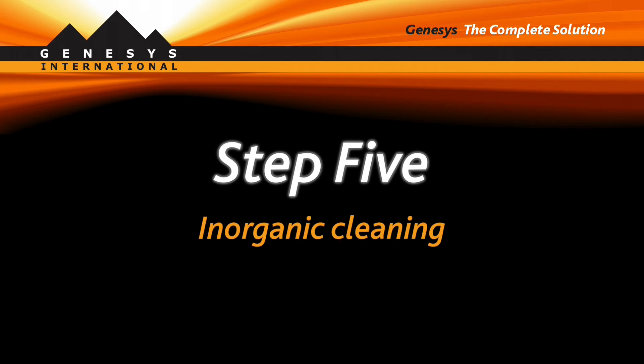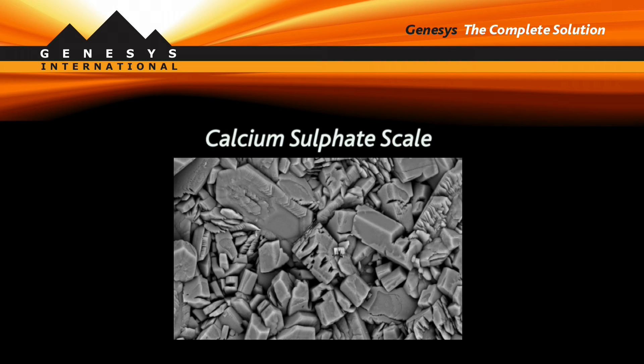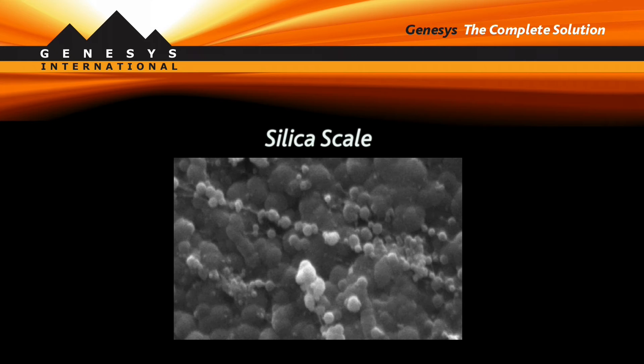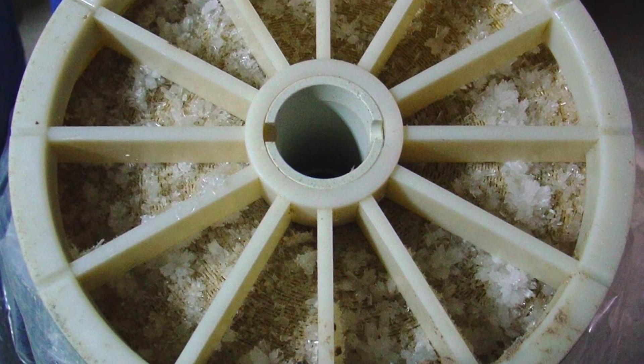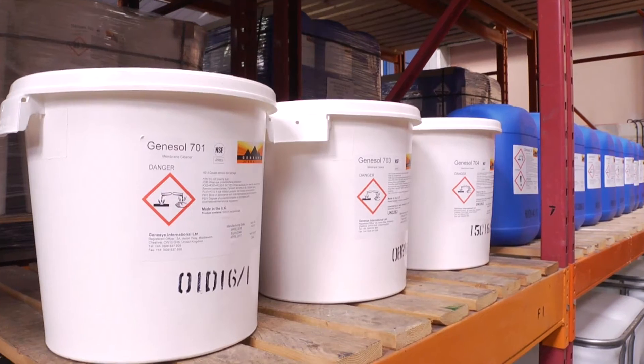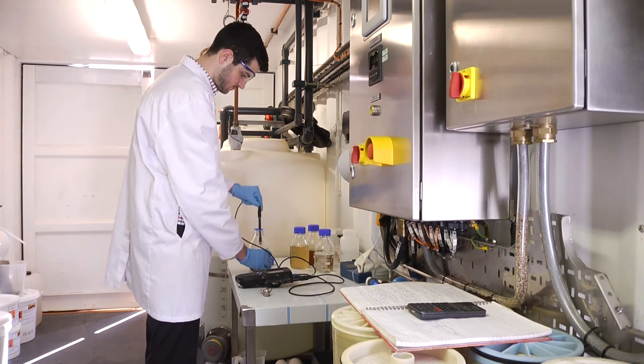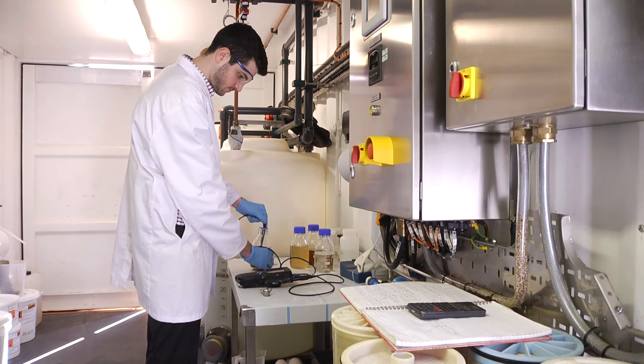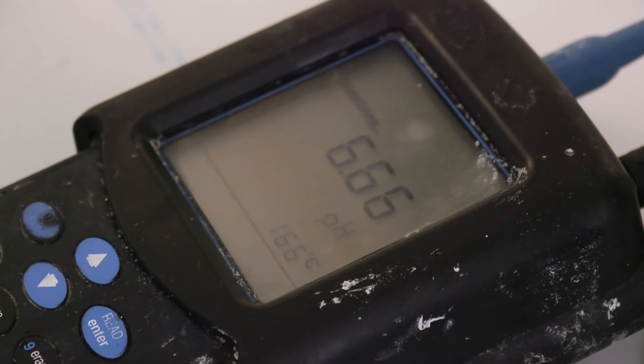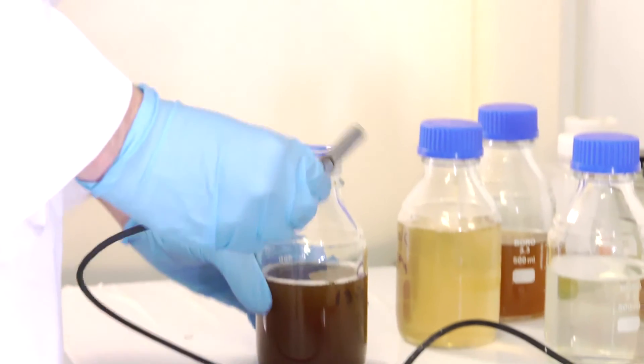Step 5: Inorganic cleaning. Inorganic deposits such as calcium carbonate, calcium sulphate, and silica occur on the final elements of the last stage. Metals can deposit throughout the system. Calcium carbonate and iron can be cleaned with Genesol 701, which is a mild acid cleaner with effervescent microbubbles. The 1% solution should be maintained at 25 degrees centigrade (77 degrees Fahrenheit) and pH should be monitored. Any pH reduction indicates scale removal; discolouration indicates iron removal.